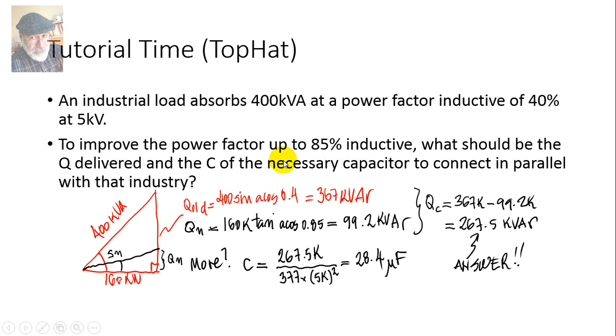How are we going to do that? We can compute the new Q. P stays the same, 160 kilowatts, but now we multiply this by the tangent of the new theta angle - the tangent of the arccosine of 0.85, since that's the new power factor. That gives us QN, 99.2 kilovars.